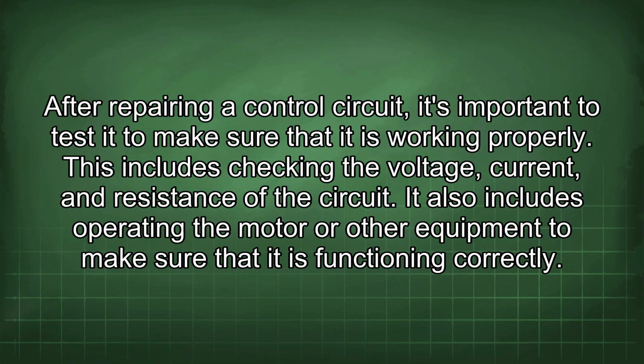After repairing a control circuit, it's important to test it to make sure that it is working properly. This includes checking the voltage, current, and resistance of the circuit. It also includes operating the motor or other equipment to make sure that it is functioning correctly.